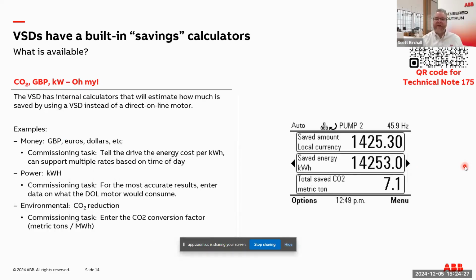So the previous slide was about metering capability. We also have calculators built into a lot of drives out there, looking at the same type of things. We start by looking at kilowatts and then figure out what we can get from that. The drive is smart enough to know the affinity laws and how much power a motor across the line would consume, but because it's slowing the motor down, it can give you an estimate of how much energy you're really saving by using a drive there.